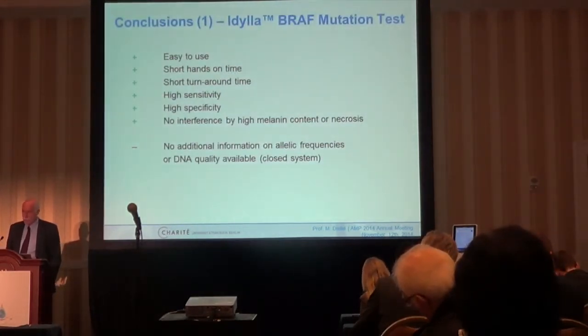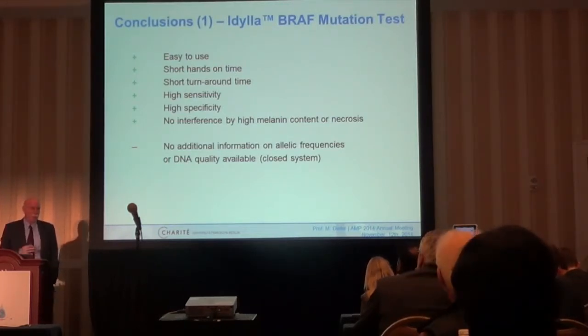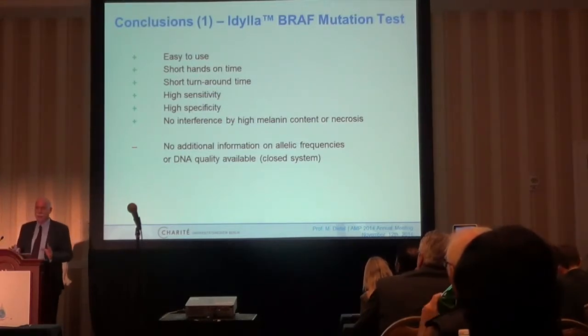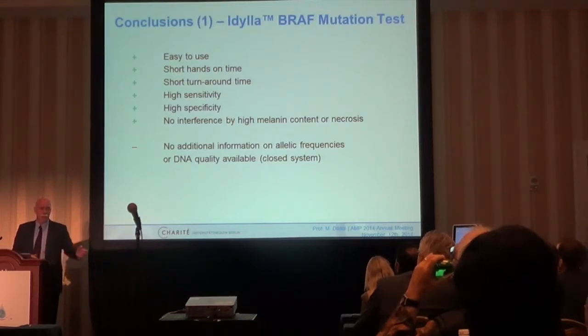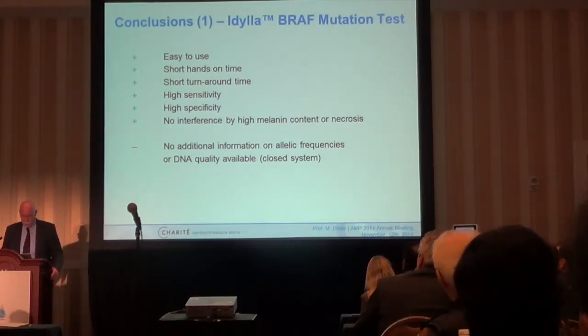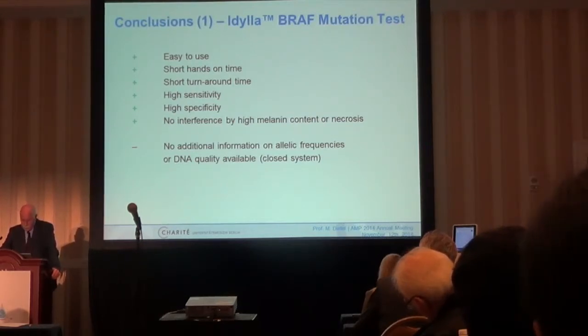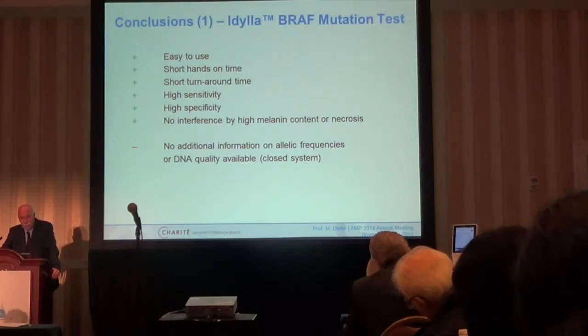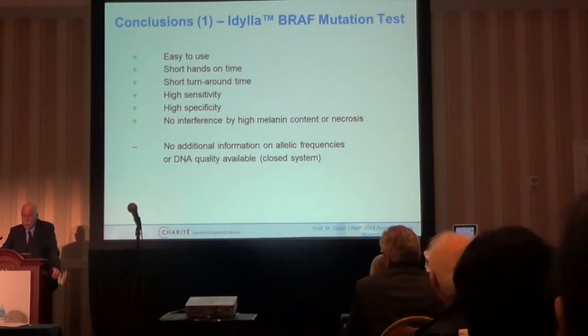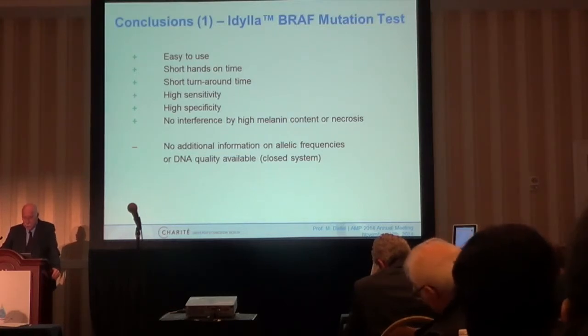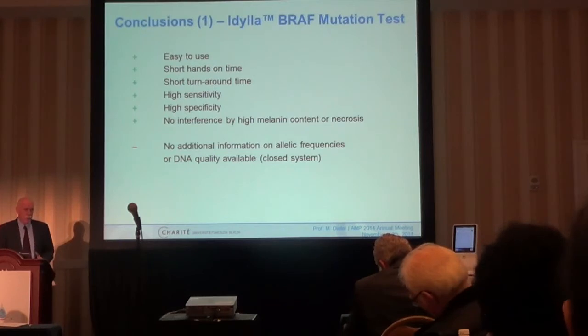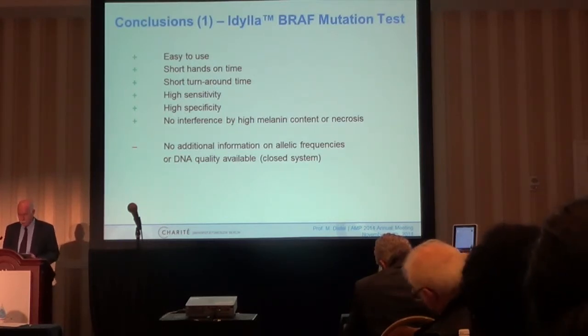Conclusion one: it's really easy to use — my technicians were delighted. You can really take a non-specialist to run it in your lab. Short hands-on time, short turnaround time — it works nicely within two hours. High sensitivity, high specificity, no interference from melanin pigmentation or necrosis — I think this is important. What is the problem? For example, in Germany we have the quality assurance program QUIP — quality in pathology — and there we have to report the allelic frequency, and that is currently not possible with this system, though maybe there can be a change later on.